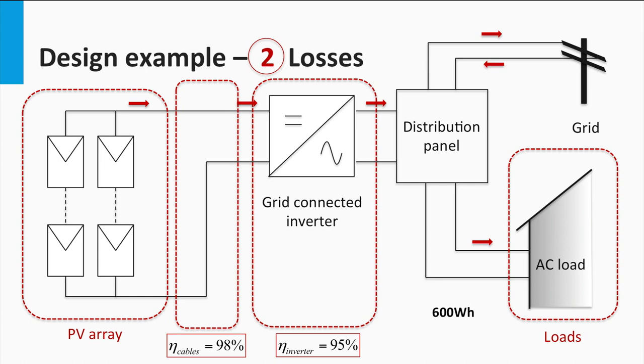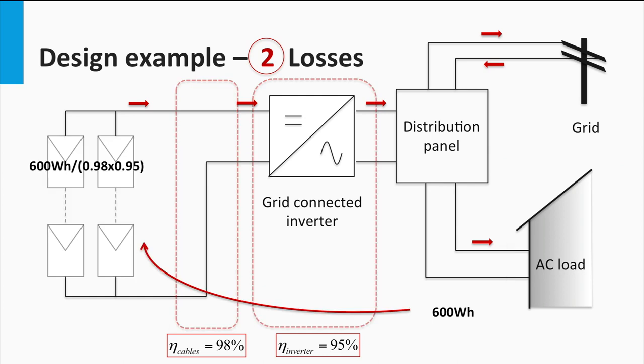Here we assume the same component efficiencies as we saw in the earlier example. That is, the cables have a transmission efficiency of 98% for the DC power, and the grid-tight inverter shows an efficiency of 95%. We also see that the AC load at the inverter end demands a total of 600 Wh during the day. Given the system component efficiency, we can then calculate the equivalent energy required from the PV panels as shown. This is basically the transposition of the energy before all these losses occur. Therefore, the total energy requirement for the PV array is 644.5 Wh.